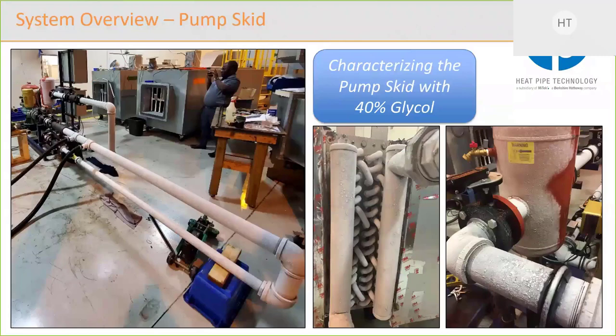An interesting point on that is actually its behavior is dependent upon what it's flowing through. So if it's flowing through a coil versus through a big pipe, the geometry around the glycol actually affects the viscosity. So it's very informative for us to have done that testing, but that also shows that there's value in our ability to test these things and make sure that we can predict what the glycol is going to do.